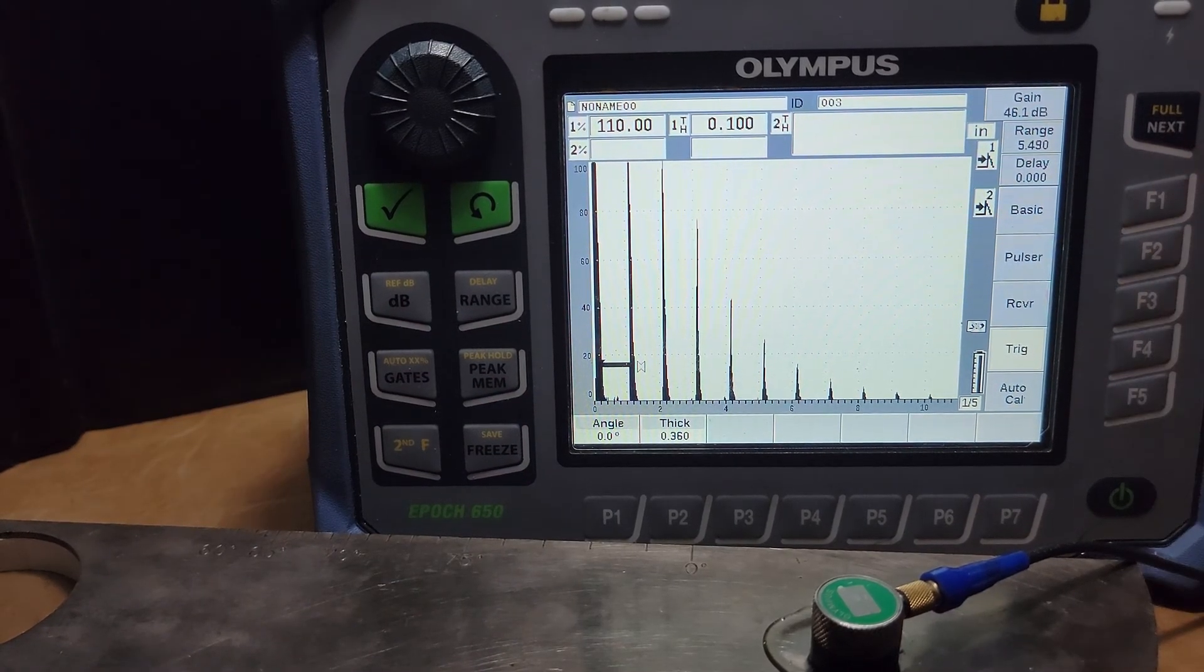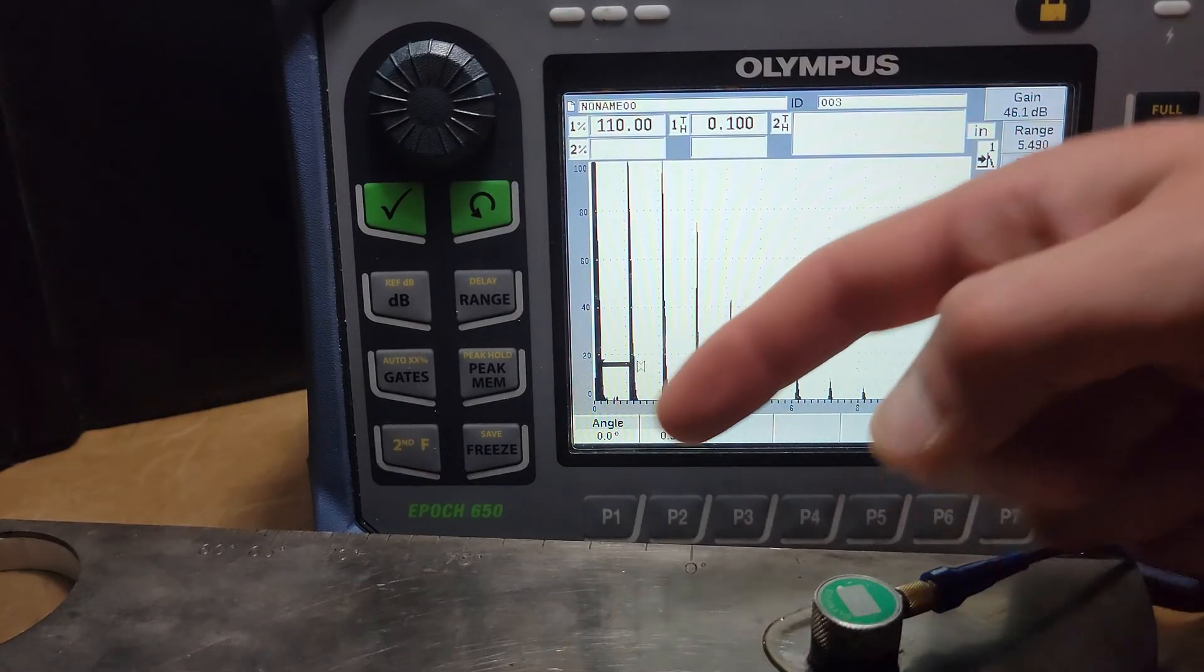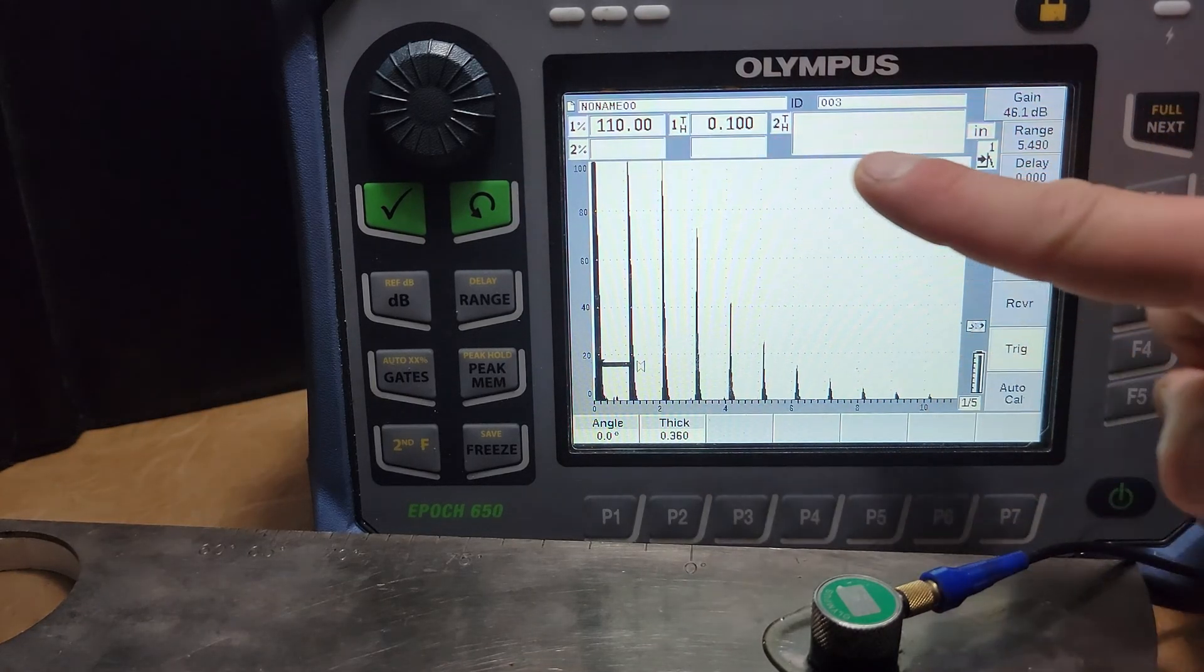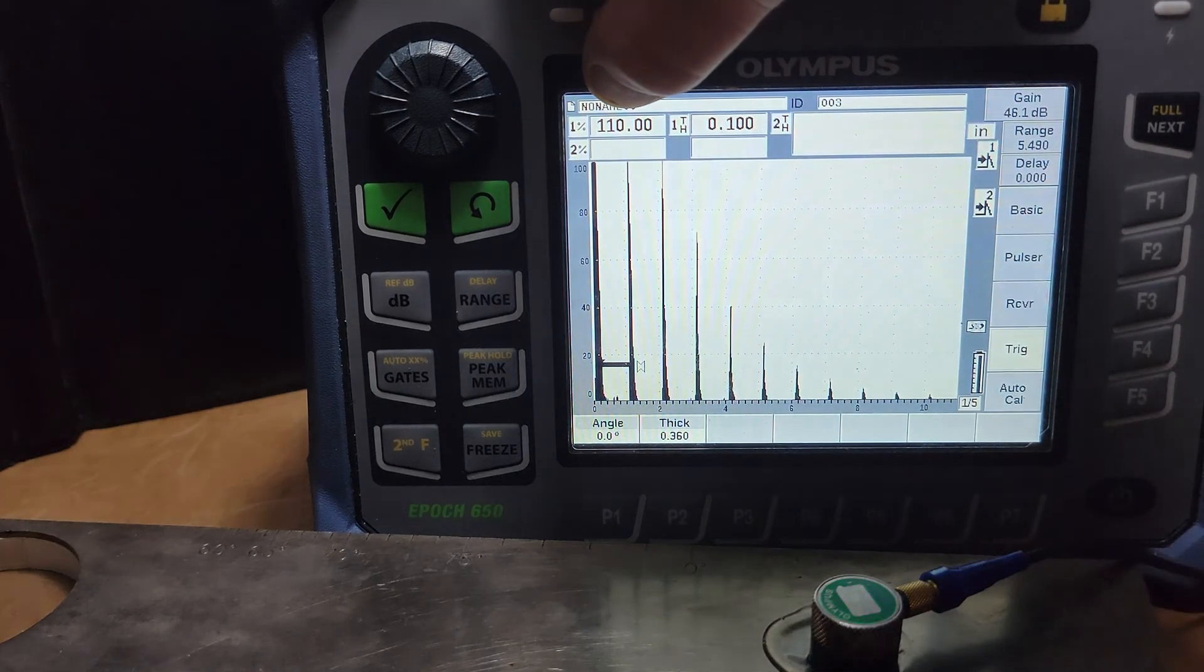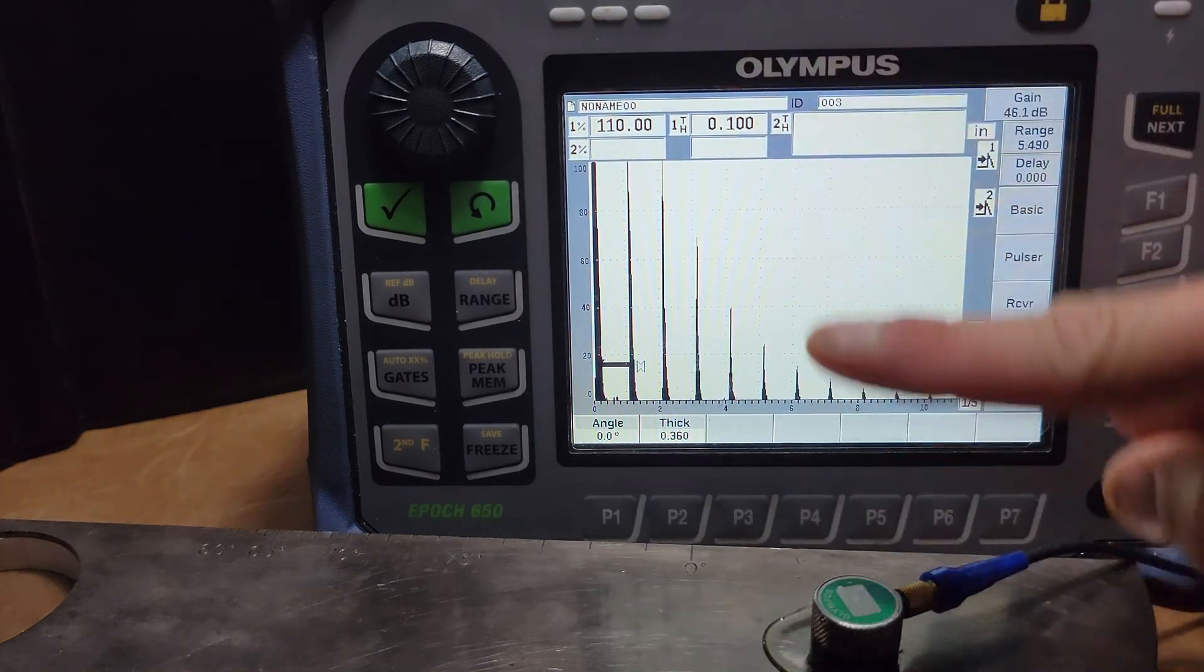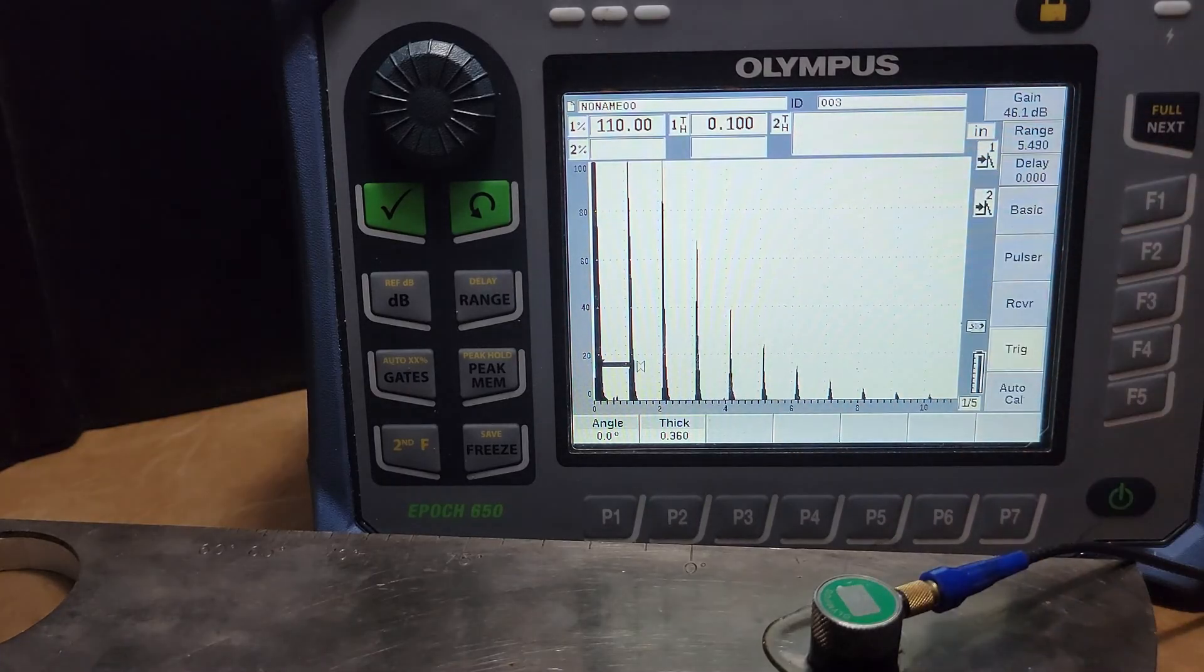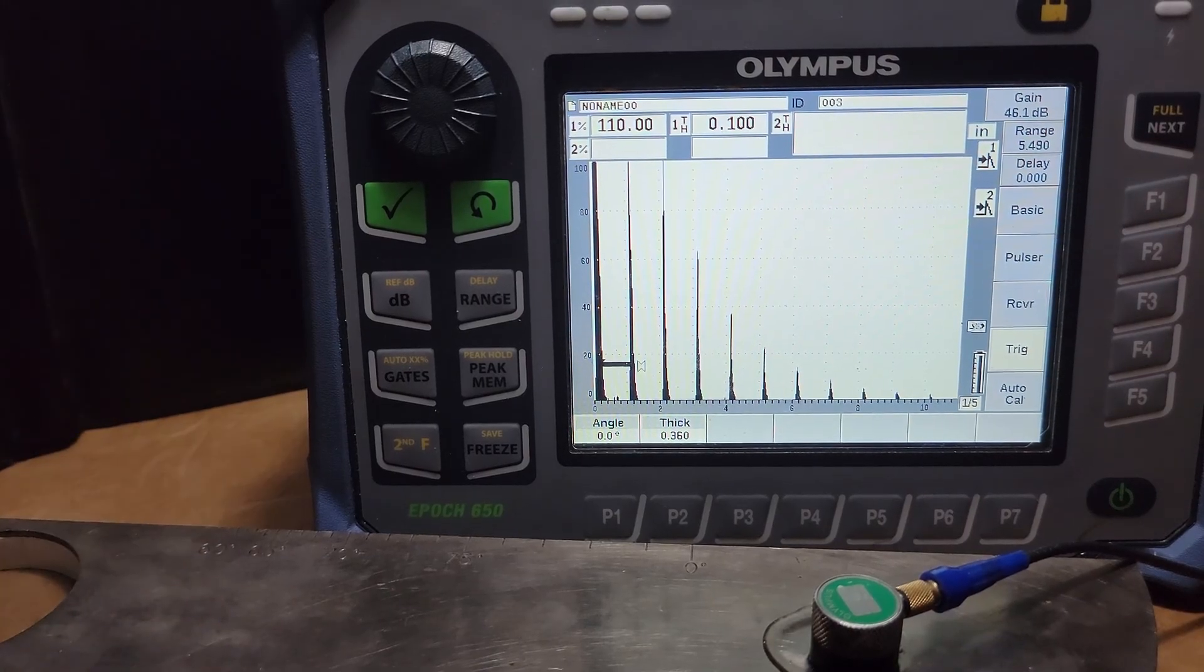Trig, make sure your angle is set to zero. Another thing that could impact our measurements: up top here you'll notice we've got gate one percentage of screen height, gate two percent, gate one thickness and gate two thickness which we could also call sound path distance. And we've got an auto cal button here which we'll come back to.